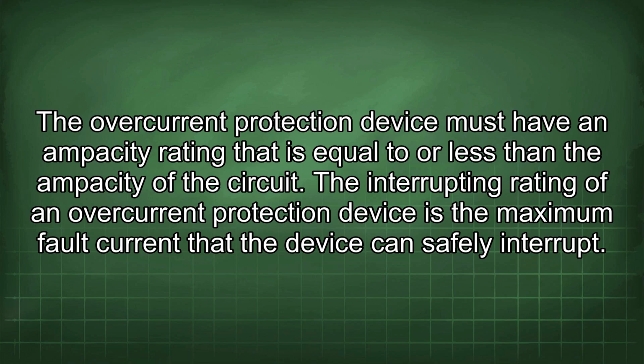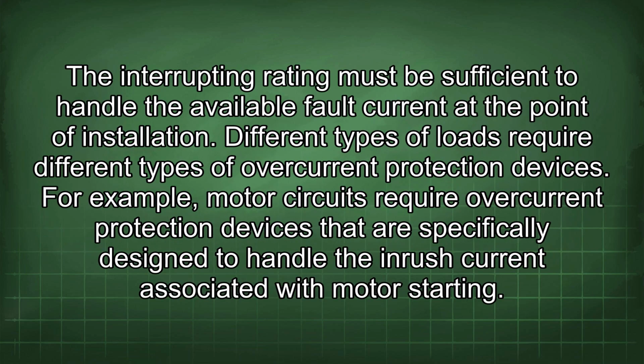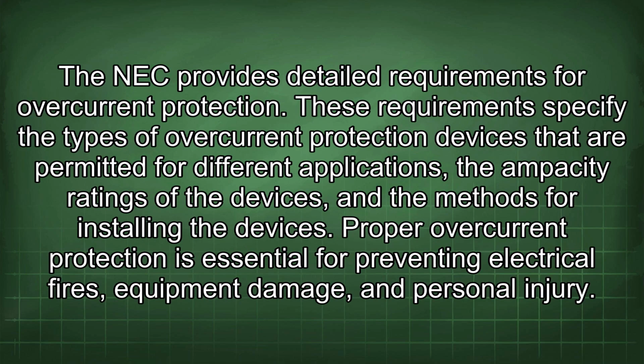circuit. The interrupting rating of an overcurrent protection device is the maximum fault current that the device can safely interrupt. The interrupting rating must be sufficient to handle the available fault current at the point of installation. Different types of loads require different types of overcurrent protection devices. For example, motor circuits require overcurrent protection devices that are specifically designed to handle the inrush current associated with motor starting. The NEC provides detailed requirements for overcurrent protection.